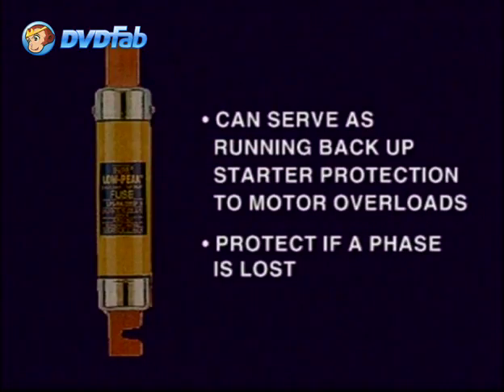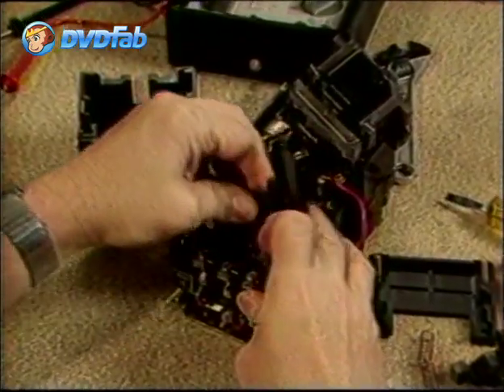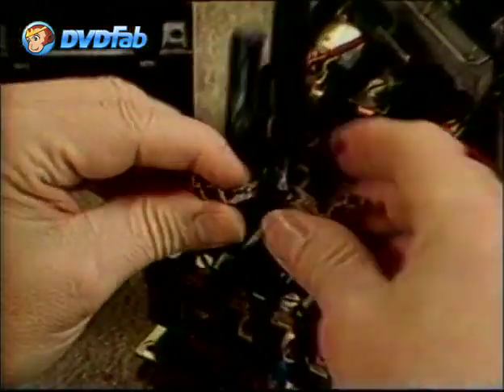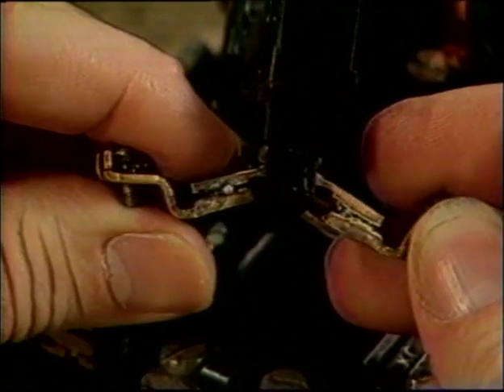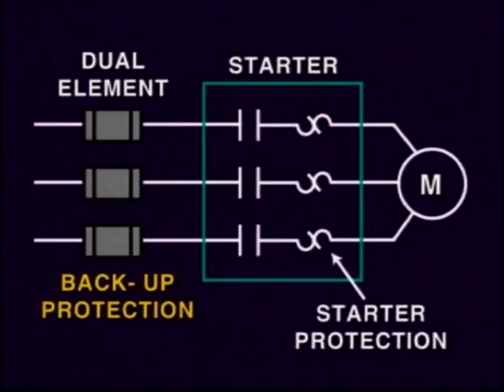In normal motor control circuit applications, the dual-element time-delay fuse, like this high-performance, all-purpose low-peak yellow, could serve as an invaluable motor-running backup protection to the motor starter overloads. This could be of particular help if a phase is lost or if the magnetic starter's overload contacts fail to open, but the power contacts remained closed because a severe overload has melted the contacts. In this case, the backup protection provided by the dual-element fuse will save the motor and circuit.